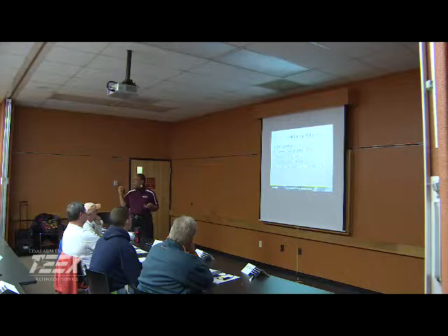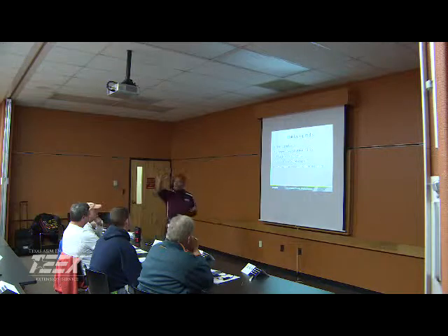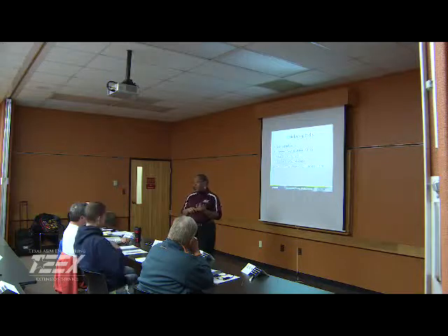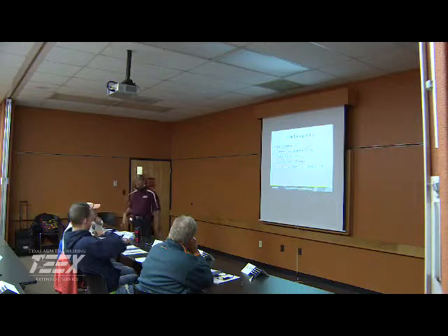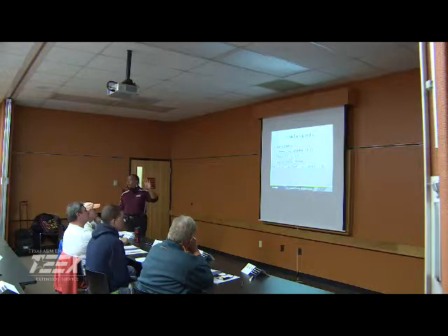What's that dechlor you use, Charles? Captor, dechlor? Captor, that's a new name, it's a brand name? Yeah. Okay, because I'm not familiar with Captor. Okay, so yeah, you can use that. Aeration, add a little oxygen, dissipate the chlorine, excellent. Or long detention time, instead of that 6 hours, longer. That will dissipate the chlorine. So those are all methods of dechlorinating. Pull those samples, no coliform, good to go.